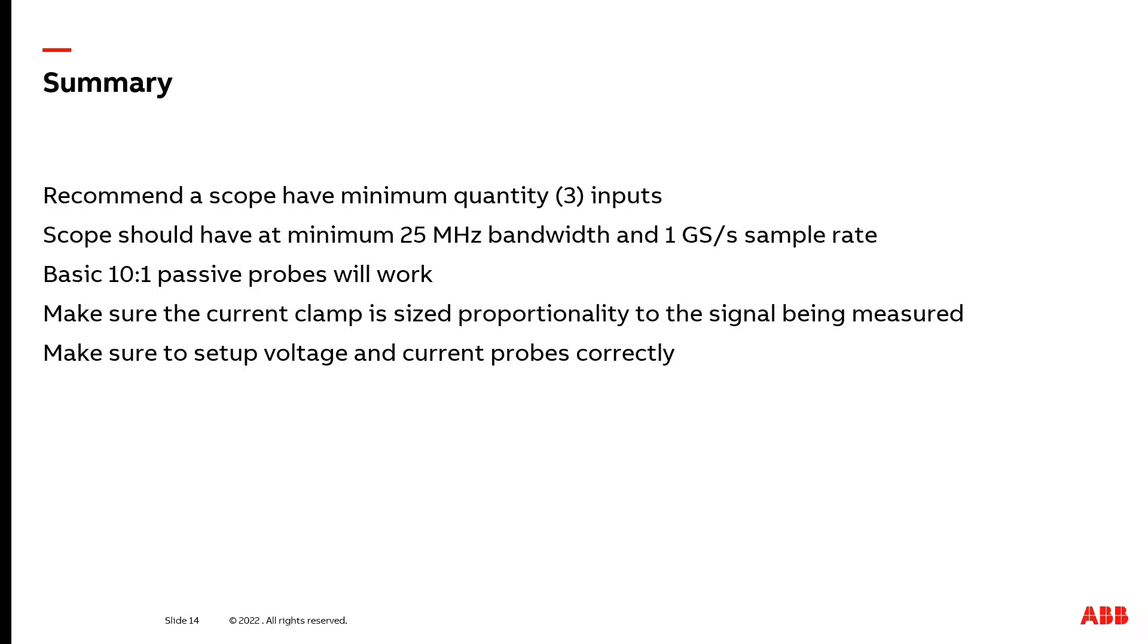Like I mentioned before, in our HVAC lab at ABB, we just use basic 10 to 1 passive probes. This will work for basic VFD measurements that you'll be taking, but you can always spend more money and get, for example, a high-end active probe. You want to make sure, when you select current clamps, that you select current clamps that are proportionally sized to the signals that you're measuring. For example, you don't want to use a 100 amp current clamp when trying to measure a 10 amp signal. Some current clamps, as I mentioned earlier, do have adjustable settings, so maybe get a current clamp that has adjustable settings, so then you are covered for multiple different current ranges.